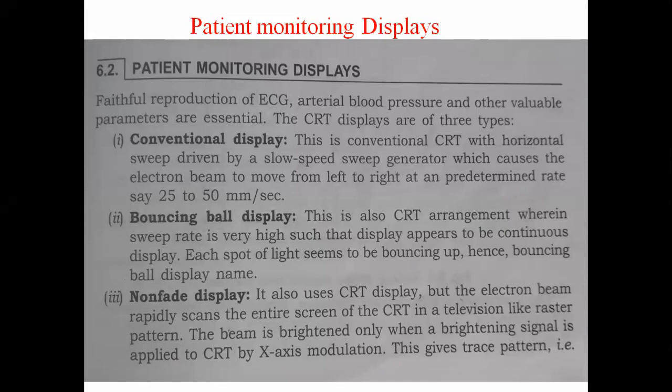variations of individual patients. So the displays may be a single display or a number of displays. It may be 8 displays at a time, so 8 signals can be displayed. Okay, so like that, the size of the CRT tubes also varies. Very small and very large sizes of CRTs are available.